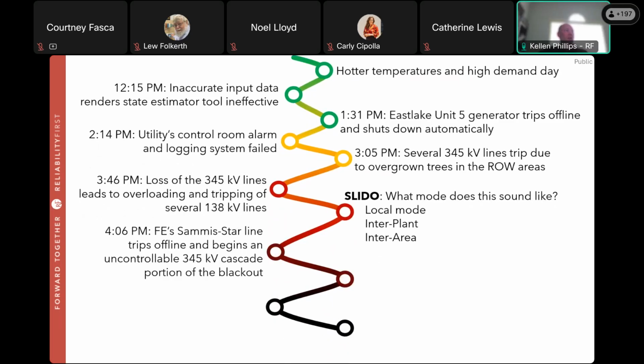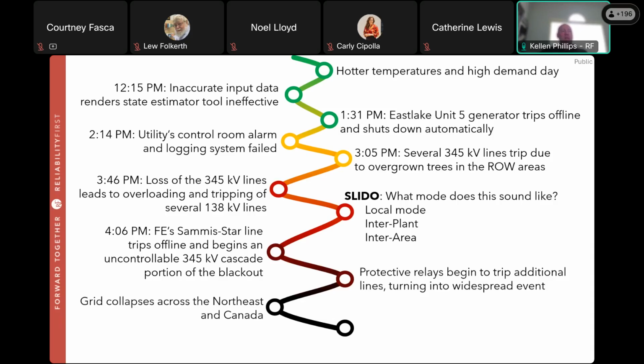At 4:06, all the line losses and surging power had come to a head at the Star 345 kV line, which was suddenly loaded at 120% of its rated capacity, therefore causing its relays to assume a fault had occurred and tripped the line. After Star tripped, within 6 minutes, low voltages, big power swings, and accelerated line tripping would cause separations and blackout within the eastern interconnection. It happened so fast that operators had no opportunity to mitigate the cascade, and the grid collapsed across the Northeast and Canada, affecting 50 million people across 8 states and Ontario, Canada.